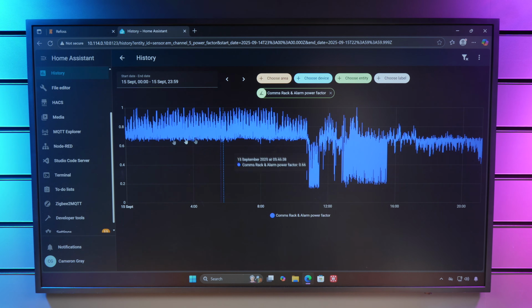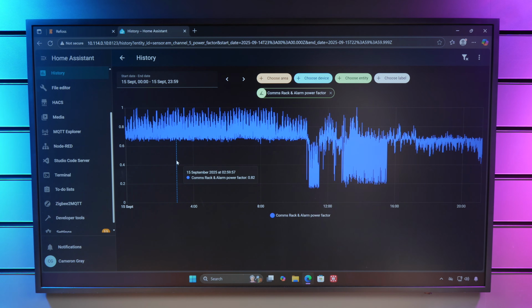But as you can see, if you look at these measurements here, it's fluctuating massively. So you can see around about here, it's jumping anywhere from 1 all the way down to 0.7. So the bottom of this line here is about right for the power factor, but we've got these massive spikes coming up, and that means it massively over-reports the power.